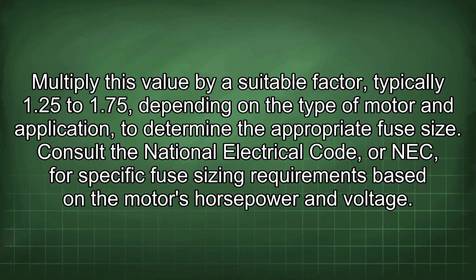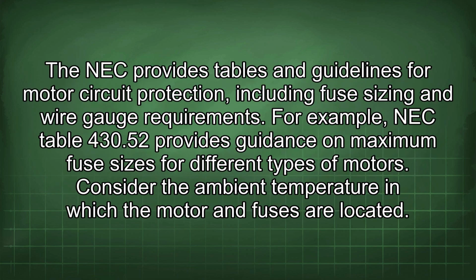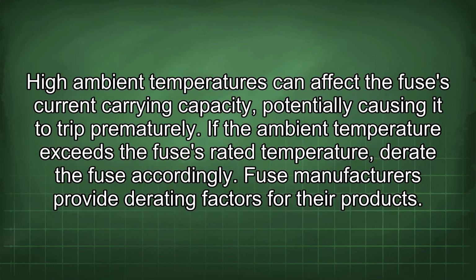Consult the National Electrical Code, or NEC, for specific fuse sizing requirements based on the motor's horsepower and voltage. The NEC provides tables and guidelines for motor circuit protection, including fuse sizing and wire gauge requirements. For example, NEC Table 430.52 provides guidance on maximum fuse sizes for different types of motors. Consider the ambient temperature in which the motor and fuses are located. High ambient temperatures can affect the fuse's current carrying capacity, potentially causing it to trip prematurely. If the ambient temperature exceeds the fuse's rated temperature, derate the fuse accordingly. Fuse manufacturers provide derating factors for their products.